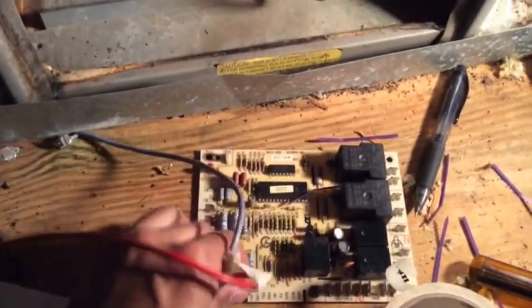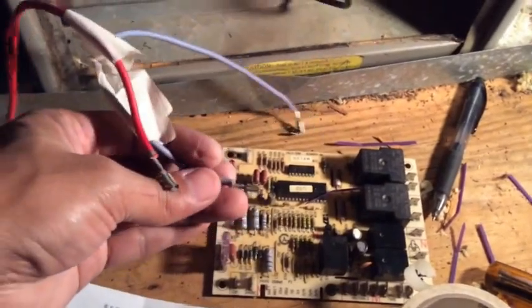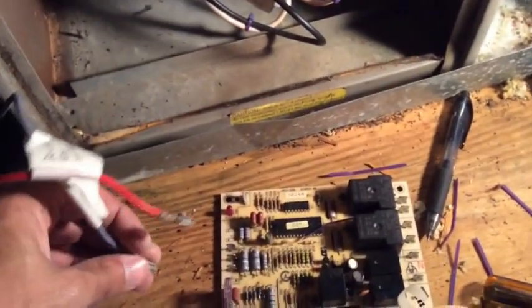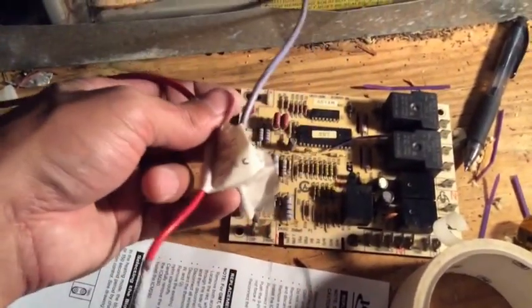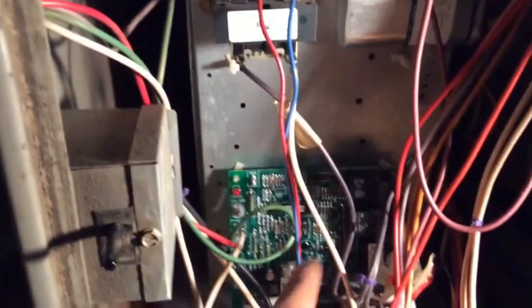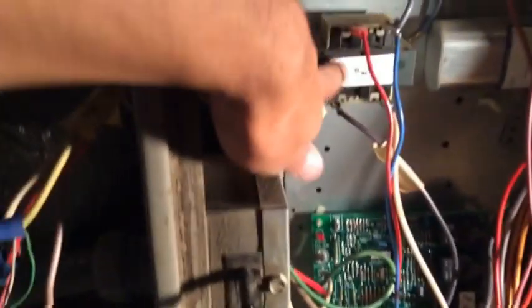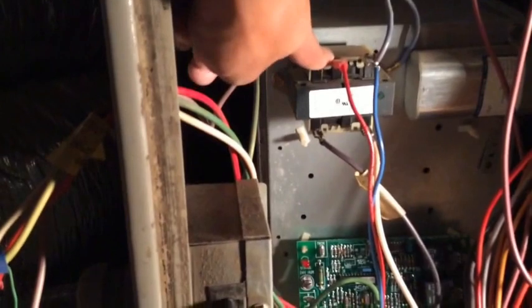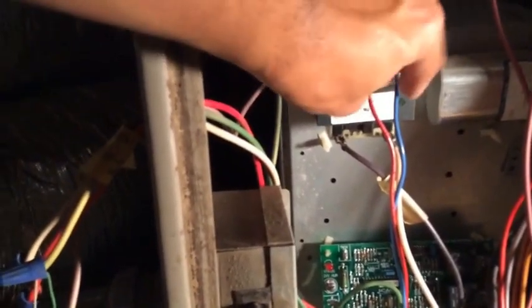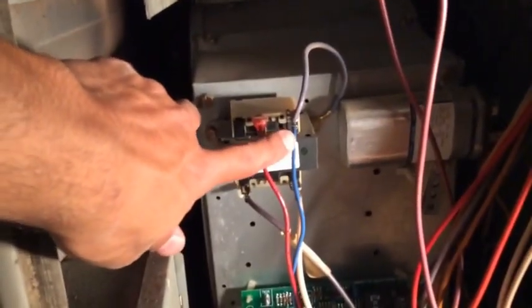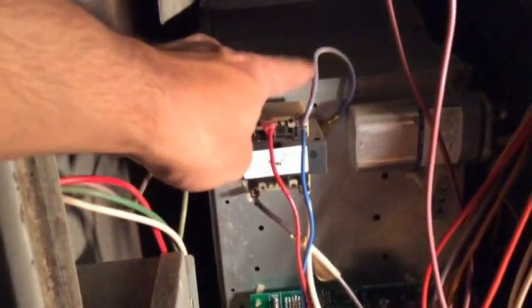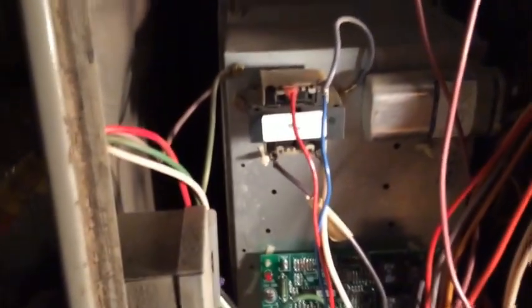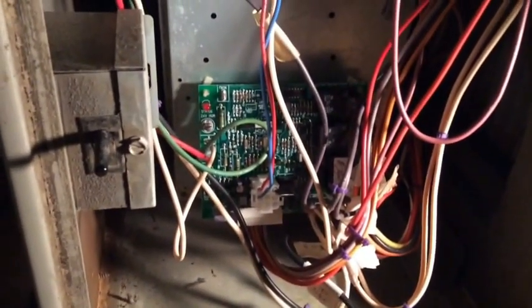Anyway, you just discard this one, as well as this ground, this neutral, which is the common, and that one just hooks up right here. Anyway, you have to discard both of these, and you hook up the red one that comes with the 9-pin connector from here to the 24 volt on the secondary part of the transformer, and then this lead here has a piggyback, which is the ground that hooks into the fan, and that common hooks up to that. Other than that, it was a pretty straightforward installation.